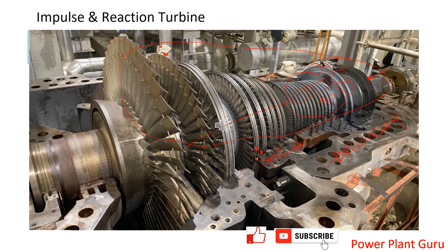This is the concept of nozzles and buckets — how different blade sizes look and why they change along the turbine. This particular section with distinct blades is your impulse stage. In different machines, certain sections are impulse and certain sections are reaction — this arrangement is called compounding of the steam turbine. Practically, you will not be able to visually tell the difference between which is impulse and which is reaction just by looking.